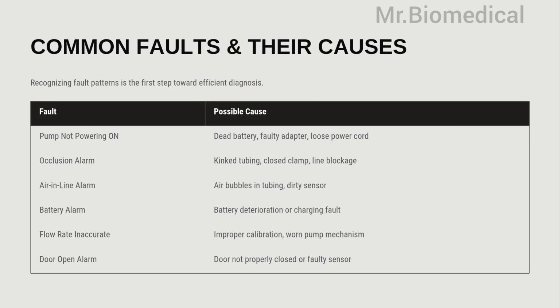Now, let's discuss some common faults encountered in an infusion pump. The first issue is the pump not powering on. This may occur due to a dead battery, faulty power adapter, or a loose power cable. The second one is the occlusion alarm. This alarm indicates a blockage in the fluid path and is commonly caused by kinking of the tubing, a closed clamp, or a blockage in the infusion line.